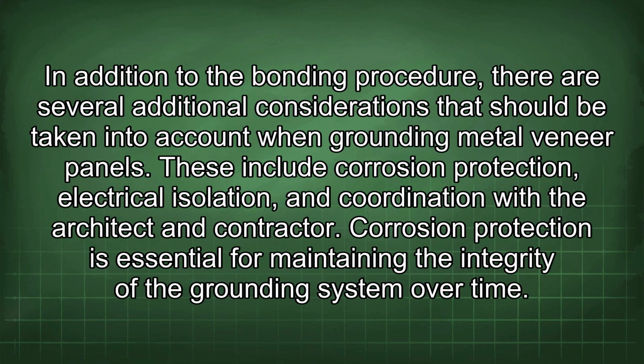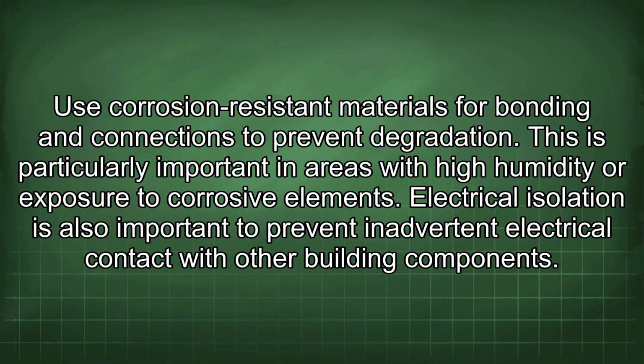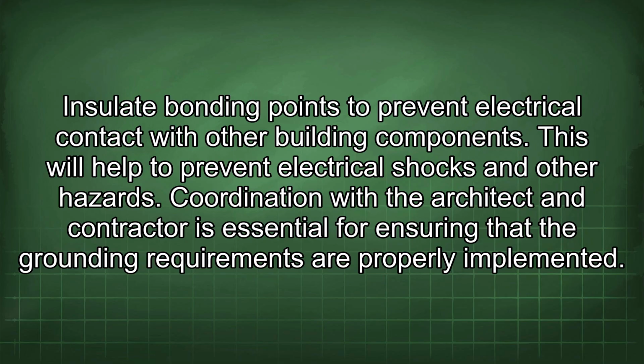In addition to the bonding procedure, there are several additional considerations that should be taken into account when grounding metal veneer panels. These include corrosion protection, electrical isolation, and coordination with the architect and contractor. Corrosion protection is essential for maintaining the integrity of the grounding system over time. Use corrosion-resistant materials for bonding and connections to prevent degradation. This is particularly important in areas with high humidity or exposure to corrosive elements. Electrical isolation is also important to prevent inadvertent electrical contact with other building components. Insulate bonding points to prevent electrical contact with other building components. This will help to prevent electrical shocks and other hazards.